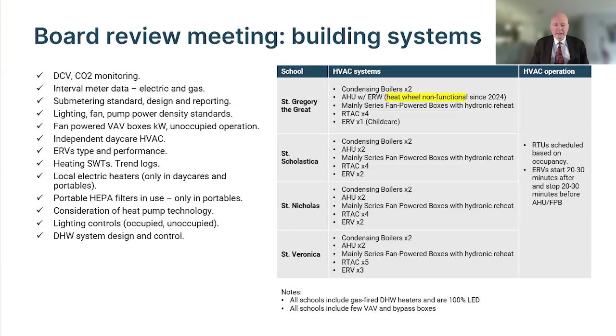We make a lot of use of interval metering, and that's going to come back over and over again. You'll see one of our recommendations is every new school should have interval metering, whether it's through the utility company or just attaching a pulse head to the meter and reading it through the building automation system. The easiest way to commission and verify a high-performing new school is through interval metering on both electricity and natural gas, and fuel oil and propane where natural gas is not available. This is very simply a picture that verifies the actual operating periods. The board's standard hours for school days are 6 a.m. to 6 p.m. Those are the 2 red lines, and these are the 4 schools stacked on top of each other. Those are the red vertical lines you see running all the way through.